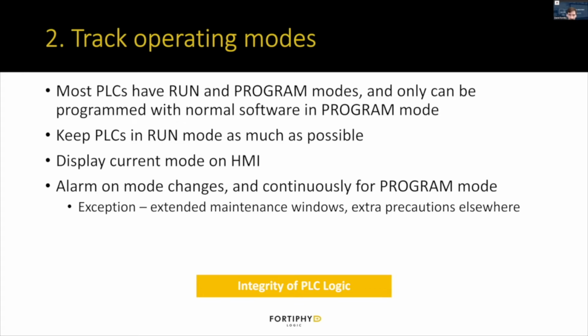The exception here, of course, is if you have extended maintenance windows, you don't need to continue alarming that it's in program mode, but just make sure you take extra precautions to lock down the PLC programming, so it's not just wide open for attackers to modify.